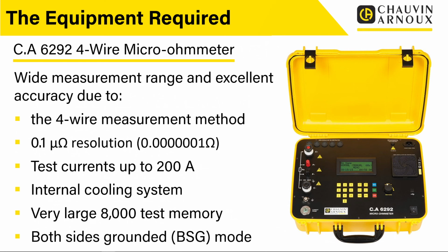And it's actually got this extra function on here, which is BSG, both sides grounded. So in some applications, you could be measuring conductors that actually are connected to ground, or may potentially have leakage to ground. And in that case, you can actually use a clamp. There's an external clamp that goes on with this, and you can connect that and actually measure the grounding current, and that then gets deducted off the readings. So actually you get an accurate reading in that sort of situation.